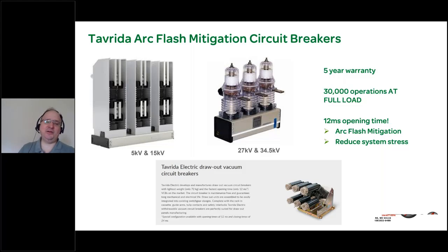But the most compelling aspect of this breaker, besides the fact that on top of all of that it's smaller and lighter than competitive breakers in the category, is that the 5 and 15 kV version has a 12 millisecond opening time. The 27 kV and 34.5 kV version has a 26 millisecond opening time. But 12 millisecond opening time is 4 times faster than even what is considered a fast 3-cycle breaker like the Evolus I just showed you. So this not only mitigates arc flash risk, but dramatically reduces system stress. So more mechanical operations, more electrical operations, less maintenance, longer warranty, and dramatically reduced arc flash incident energy are the hallmarks of this circuit breaker.